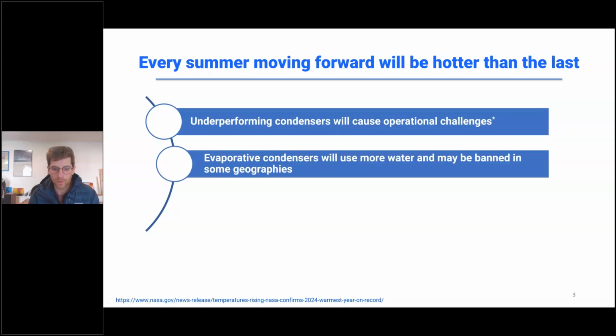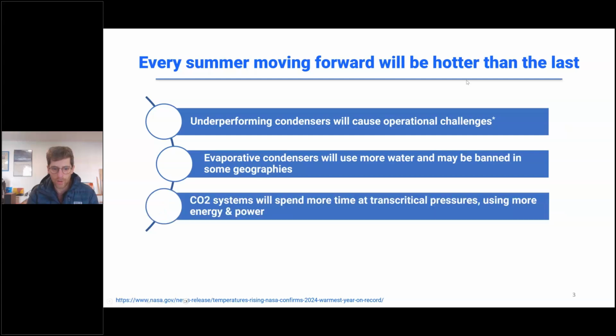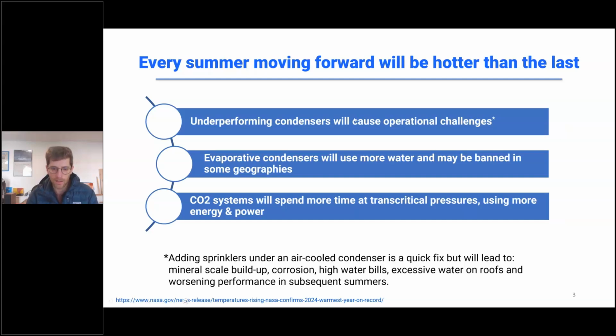Evaporative condensers will use more water. We're going to start to see evaporative condensers that can't be installed in certain regions. For example, in Las Vegas and Phoenix, there are already moratoriums on using these types of systems because they're water stressed. And as we switch to new refrigerants, there's going to be more transcritical hours, for example with CO2, and this is going to mean more power and more energy use in these systems. There's for sure the opportunity to use sprinklers on underperforming air-cooled systems, but that does lead to corrosion and other challenges.